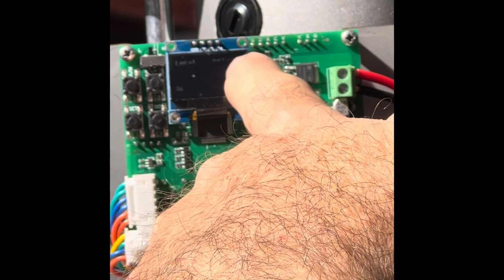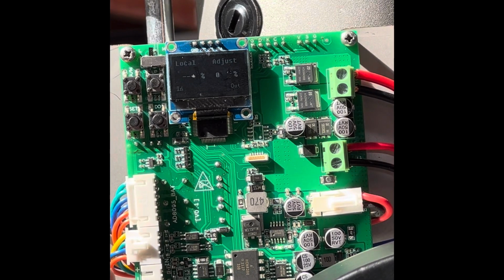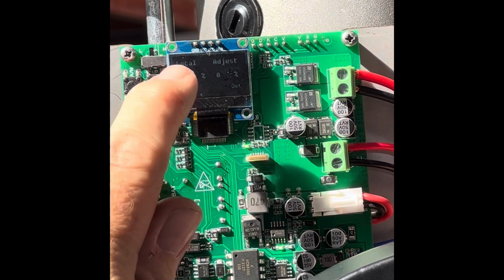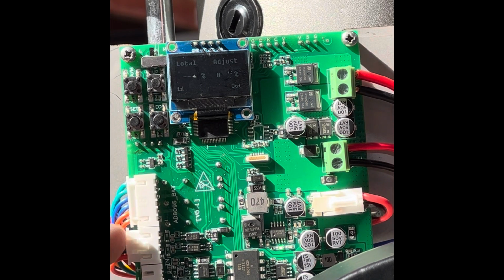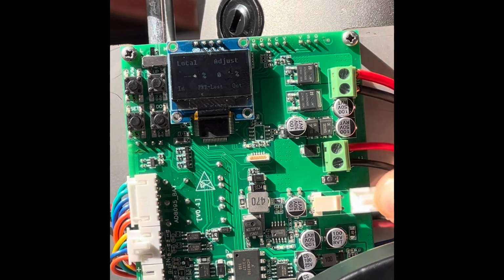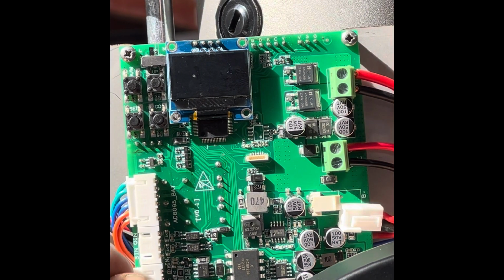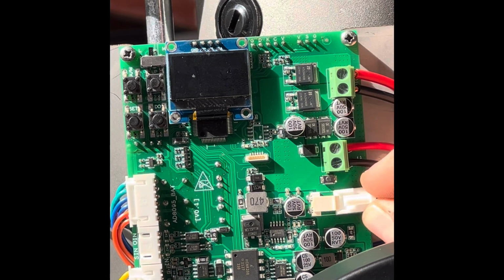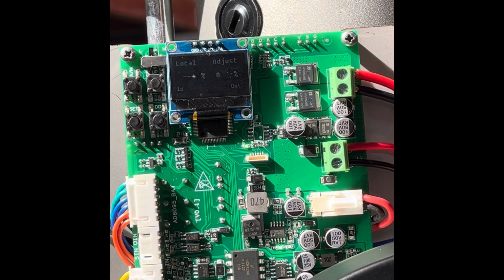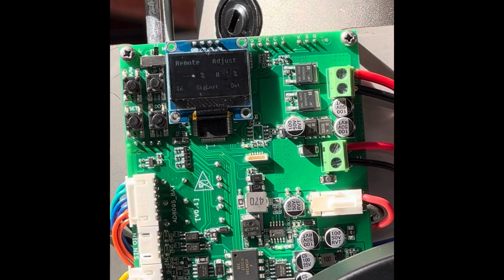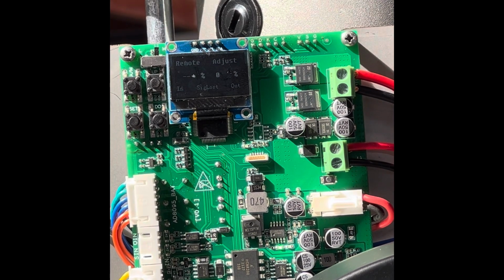Okay, now the board says adjust. So we moved from local to adjust by changing the control mode from local to 4 to 20 milliamp. Now the one thing we have to do is remember to move this. Take this plug and put it down here. Before we do that, I'm gonna cut power, unplug the battery, then relocate this plug, plug the battery in, turn the power on. Okay, now it says remote, adjust. Make sure to flip it into M position.